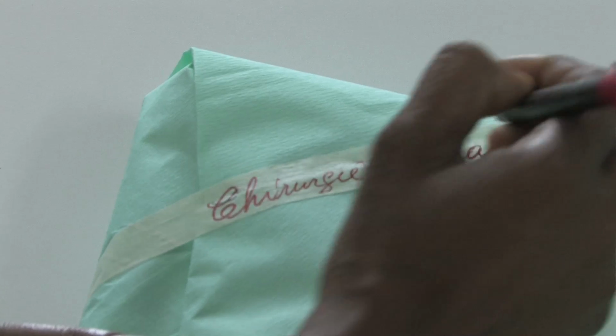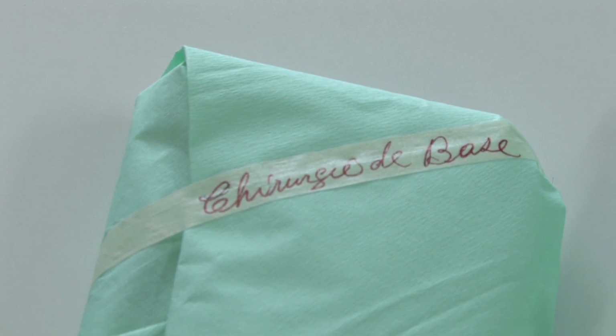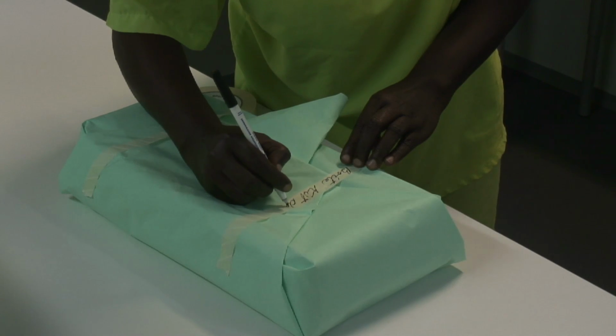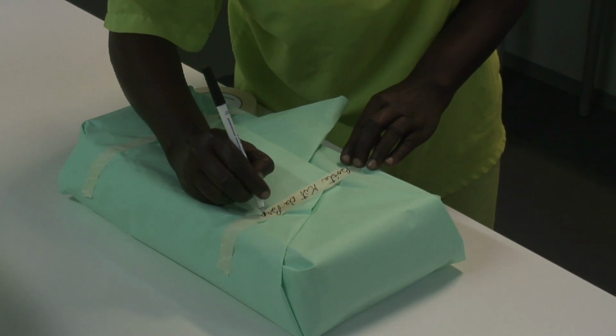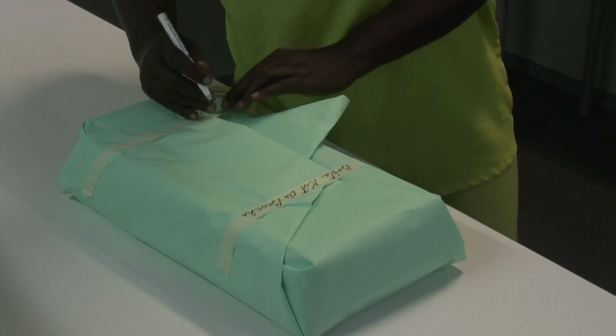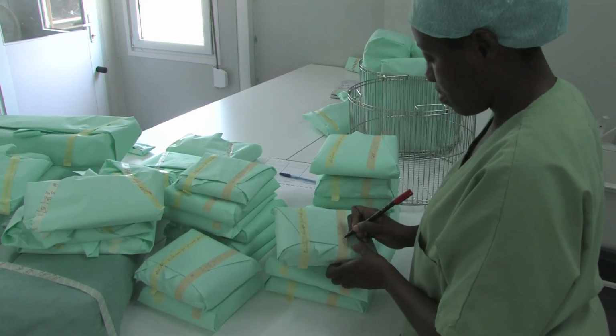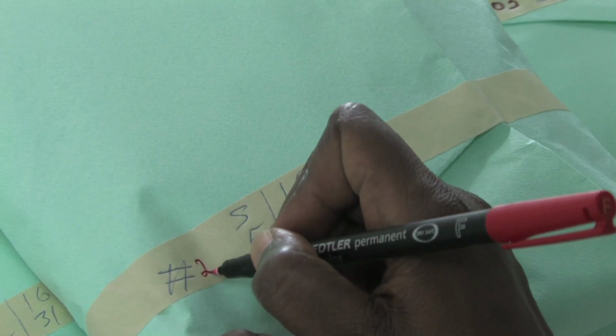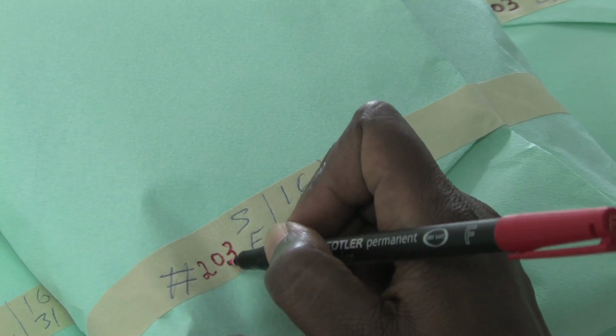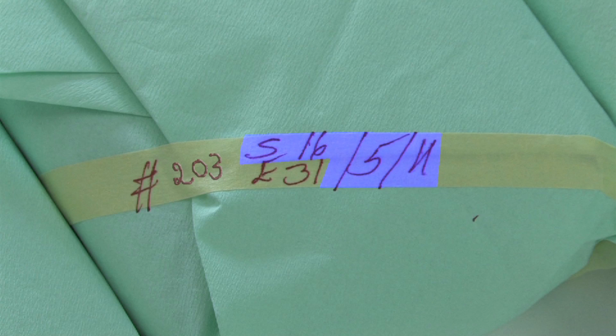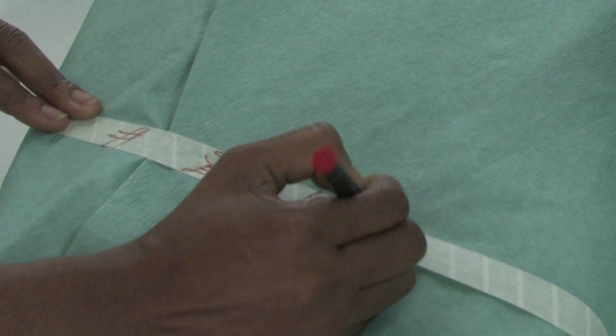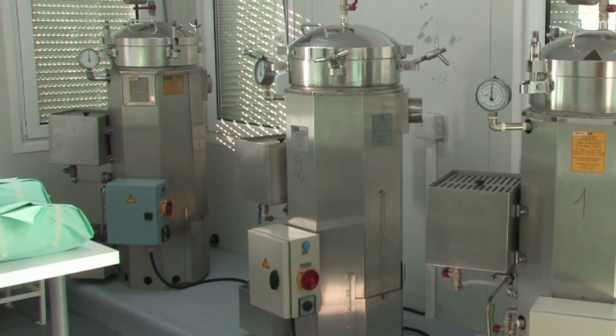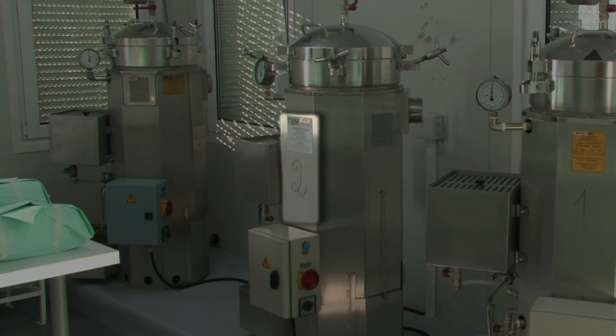Label the pack by writing the name of the set or device on the indicator tape. Use a special pen that will not pierce the wrapper and whose ink is steam-proof. Write the autoclave cycle number and the expiration date on the packaging. The expiration date should be no more than 2 weeks after the sterilization date. If there is more than one autoclave in service, write the autoclave number as well.